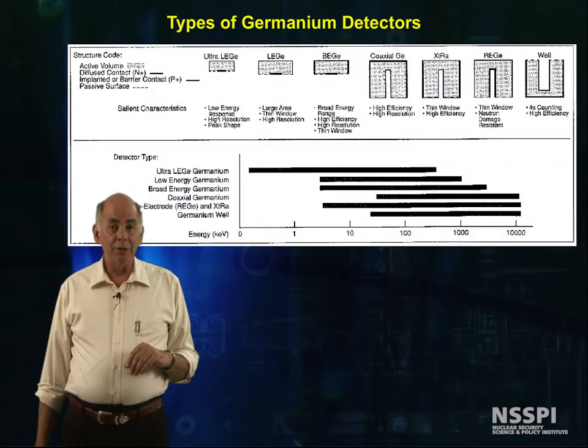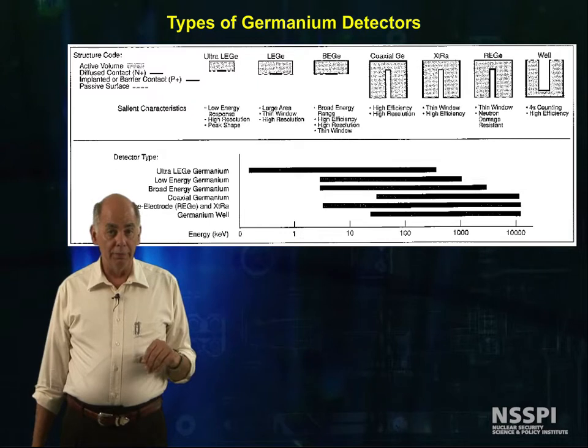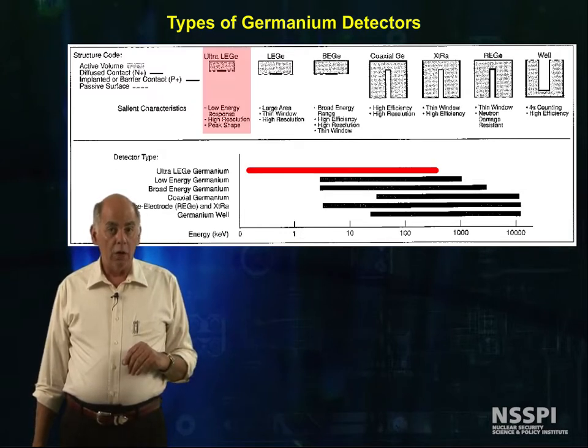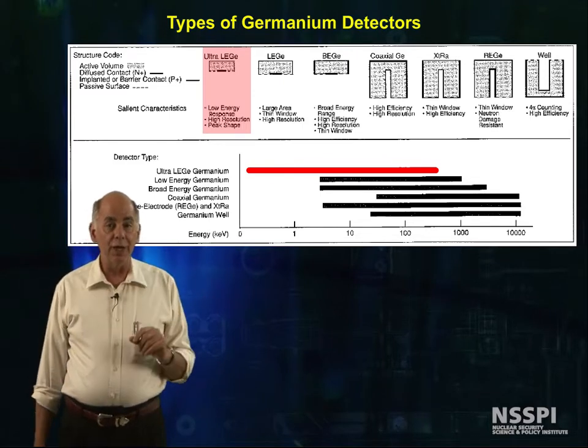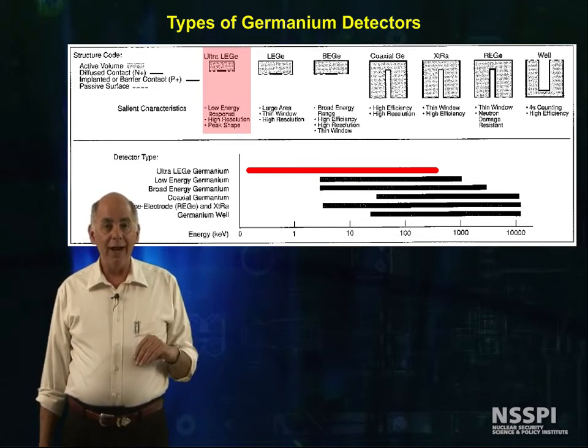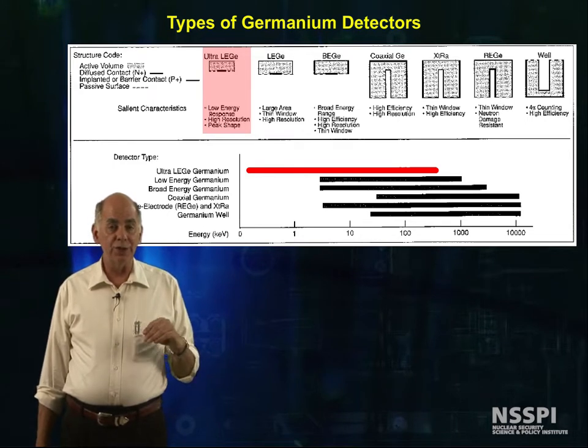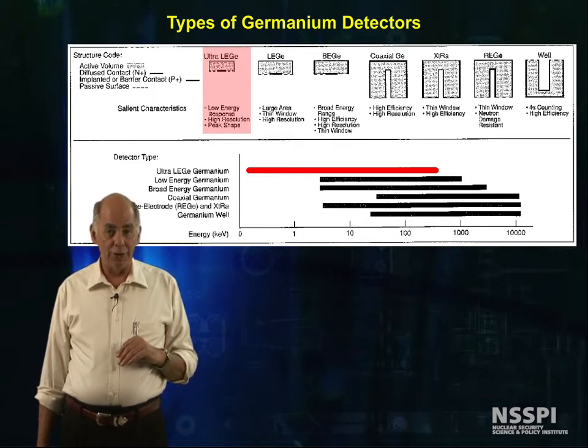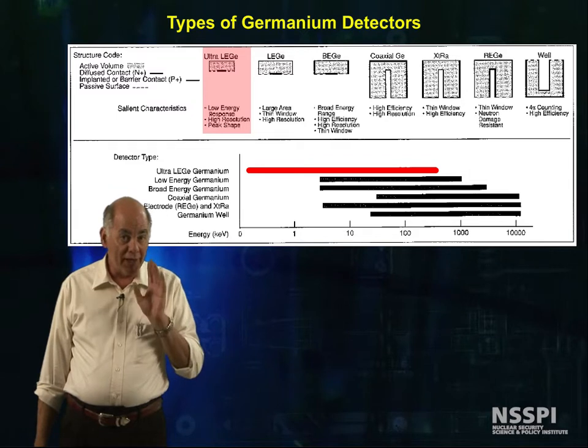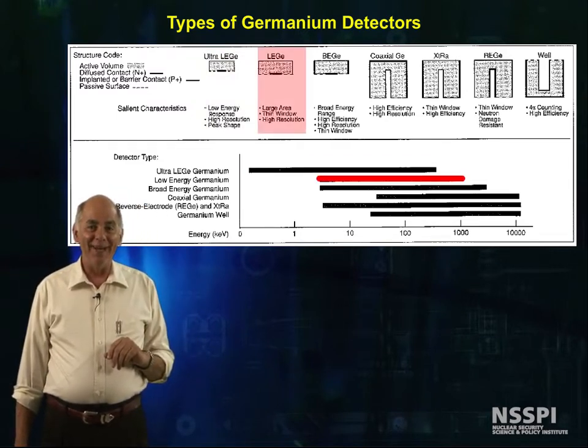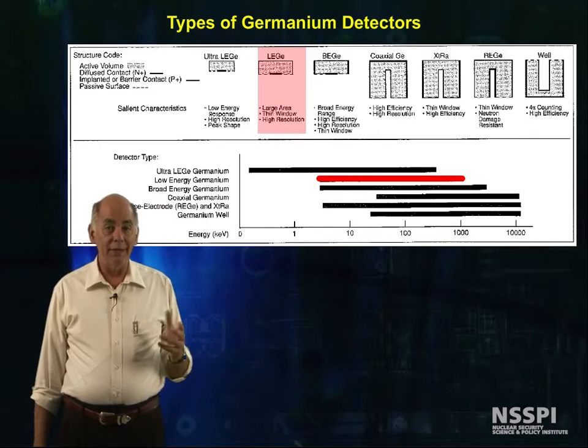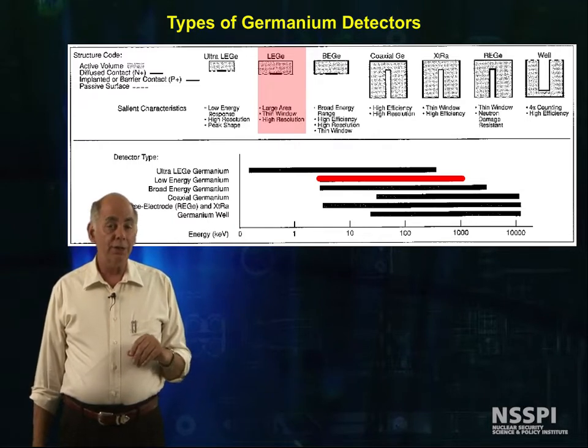Germanium detectors come in a variety of shapes and thicknesses of the p-n junction and of covering materials. Ultra-low energy germanium detectors have ultra-thin junctions and carbon fiber windows, so they can be used in the sub-keV photon range — and bring lots of money if you want one of these. Low energy germanium detectors can have beryllium windows, and the rest use aluminum.